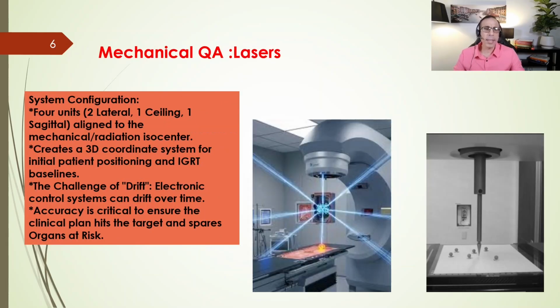Our next test is related to our visual guide of the patient positioning, the laser system. At the time of installation, these lasers are perfectly aligned to either the radiation or mechanical isocenter. In a standard setup, we rely on 4 laser units: 2 lateral, 1 on the ceiling, and a sagittal laser at the foot of the couch. Together, these create the coordinate system we use to align our patient in 3D space.